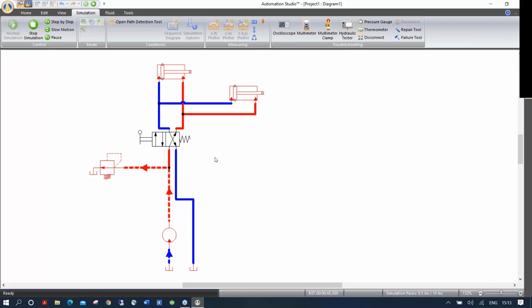This is important because I've seen customers send me circuits saying it doesn't work — they were making an electro-hydraulic circuit with a solenoid, but the spool was overridden in one position. Even though they were activating the solenoid, the valve was not shifting because of that check mark. So if students come to you and say the schematic is correct but it doesn't work, this could be the reason.